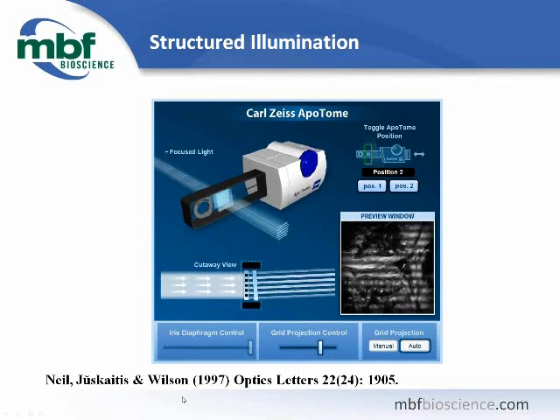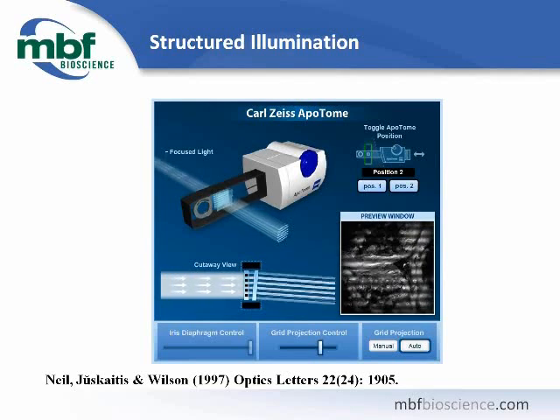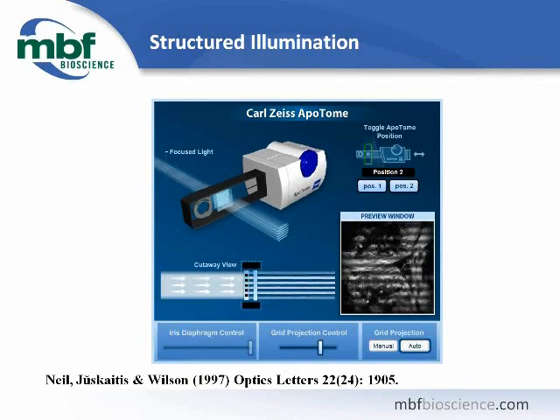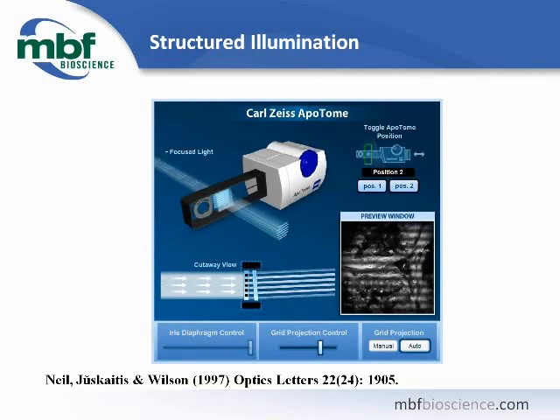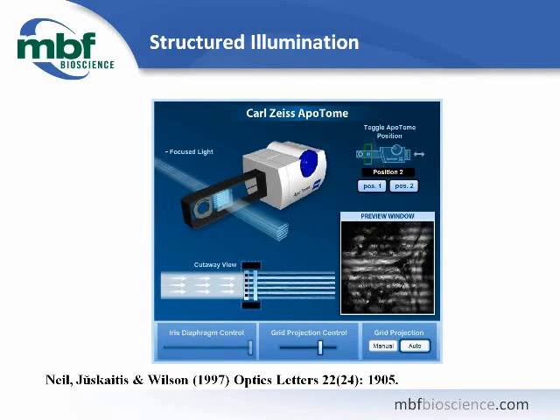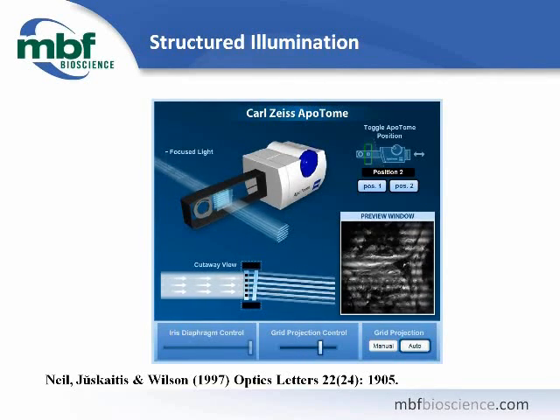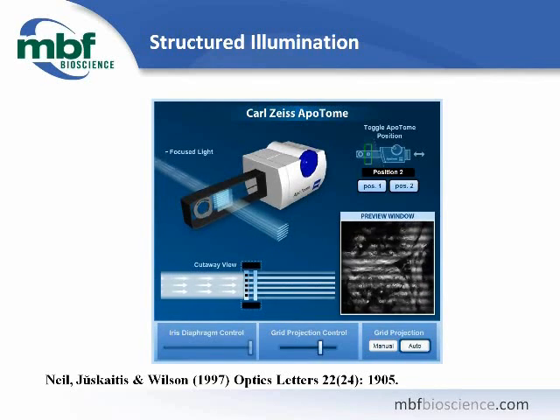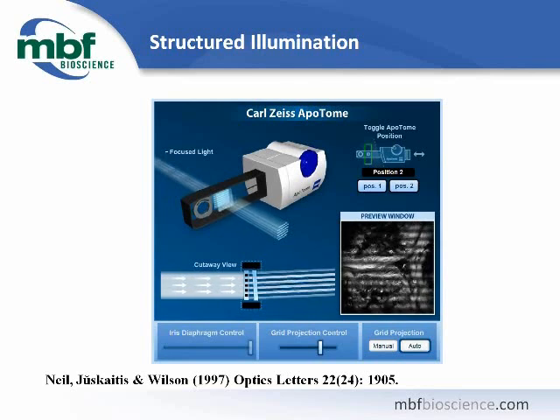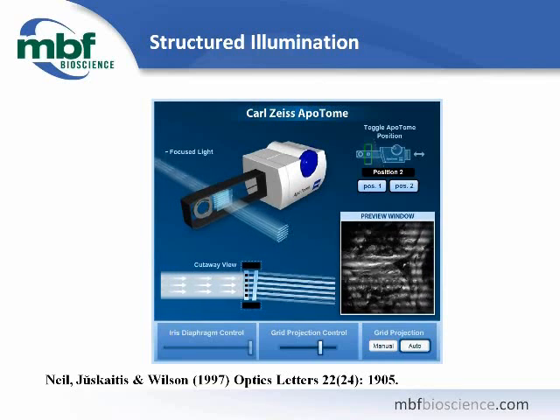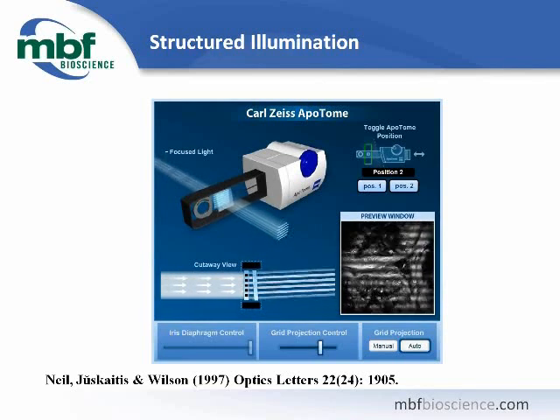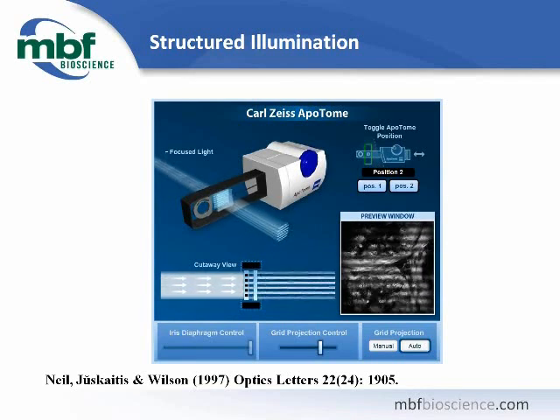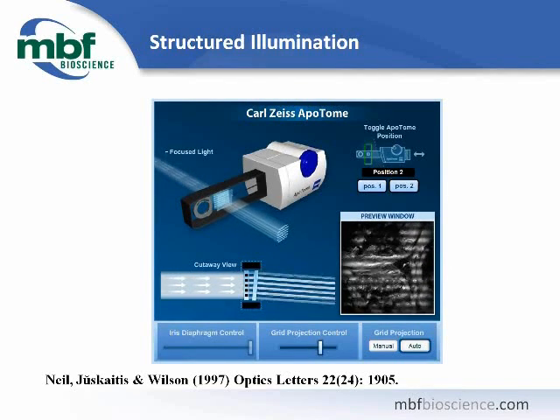I would also like to recommend reading this paper from Tony Wilson's group at Oxford. This is an early paper on structured illumination and goes into detail about the theory and mathematics involved in this particular strategy. Now we can illustrate structured illumination imaging with the Zeiss ApoTome. The strategy is to capture three or more wide-field images with the grid pattern projected into the focal plane of the objective. These component images are then analyzed, out-of-focus light is removed with the grid lines, and the final image is comprised of only in-focus light.